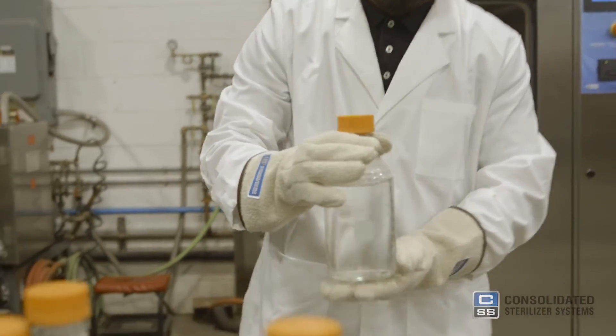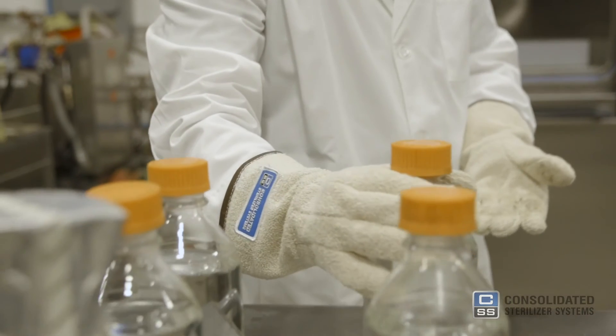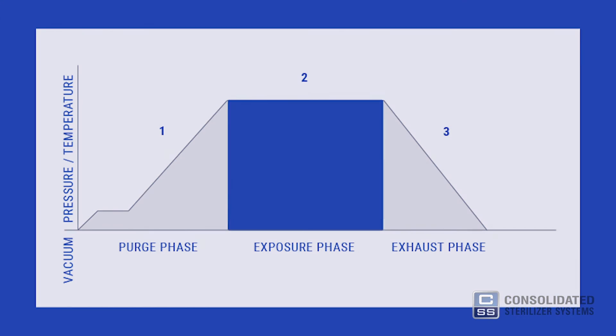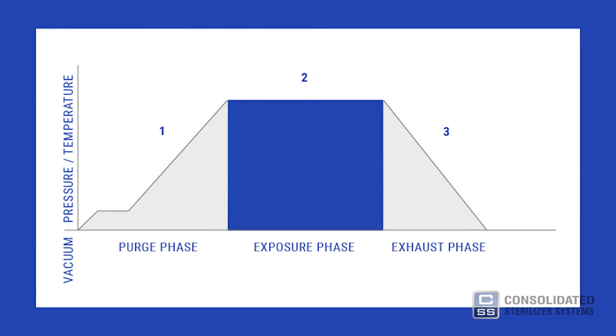There are three primary phases to any sterilization cycle. First, the purge phase, during which steam enters the sterilizer and displaces air. Second, the exposure phase, during which the autoclave achieves and maintains the desired temperature. And finally, the exhaust phase, during which pressure is released from the chamber and the chamber is restored to ambient pressure.